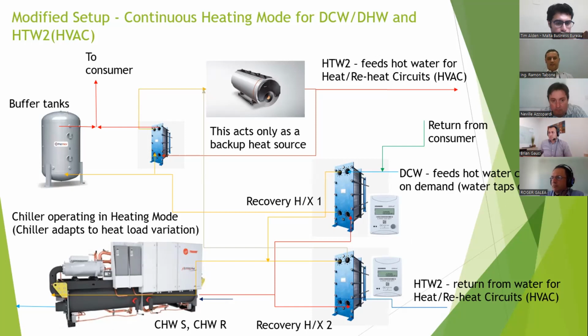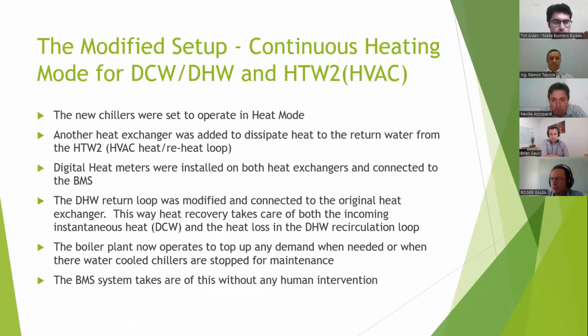With the installation as it is now, it still does not cover all the heat demand that we have. So the boiler is just there to top up the remaining demand. As I described, all engineering services here at Mater Dei are connected to a centralized building management system. I installed the digital heat meters, and that proved very important to collect data and compare.